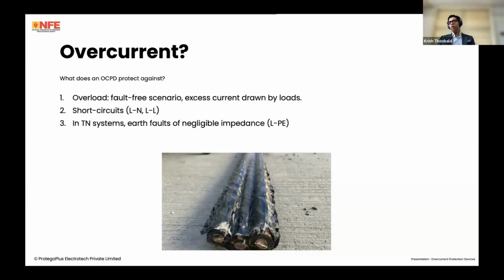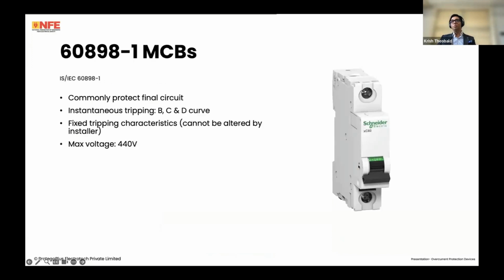Then you've got a short circuit between your line and neutral, which in India we call phase colloquially. Phase and neutral or phase to phase. And also in TN systems where your neutral is connected to your earth through a negligible impedance at your transformer, earth faults are going to have a negligible impedance, so this would essentially classify as an overcurrent. So these are earth faults of negligible impedance. These are three situations where OCPDs really step in. Overcurrents will eventually lead to fire because they lead to thermal stress. So you can see in this image here how a cable has been badly impacted by overcurrent.